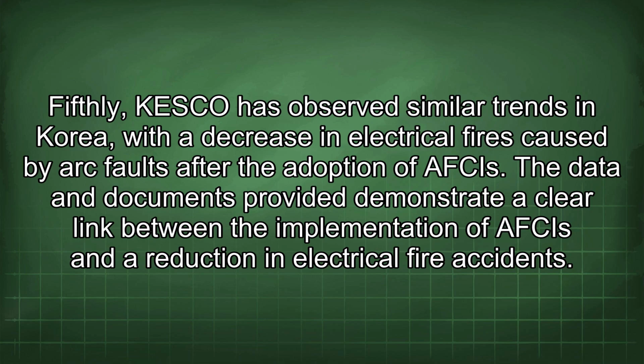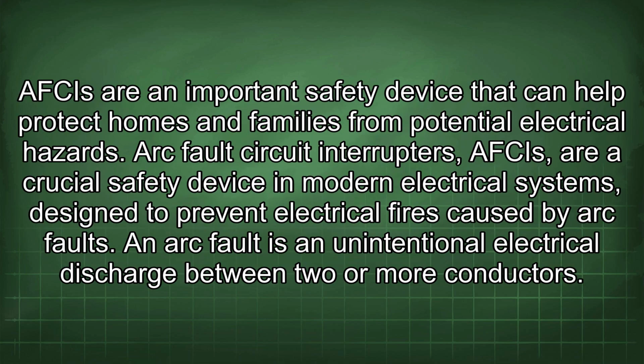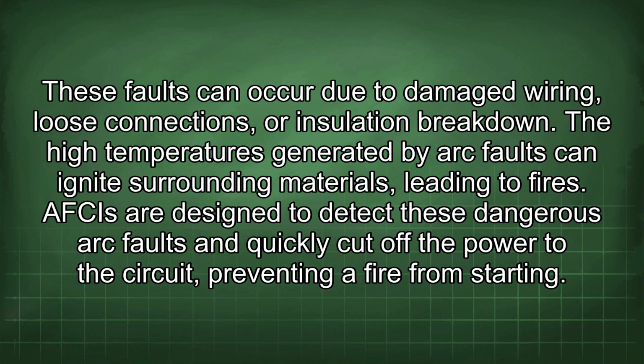in electrical fire accidents. AFCIs are an important safety device that can help protect homes and families from potential electrical hazards. Arc fault circuit interrupters, AFCIs, are a crucial safety device in modern electrical systems, designed to prevent electrical fires caused by arc faults. An arc fault is an unintentional electrical discharge between two or more conductors. These faults can occur due to damaged wiring, loose connections, or insulation breakdown. The high temperatures generated by arc faults can ignite surrounding materials, leading to fires.